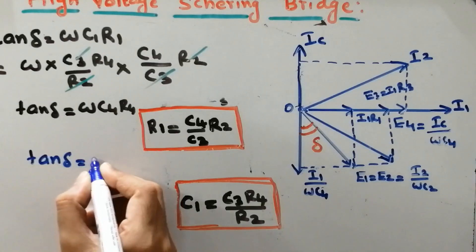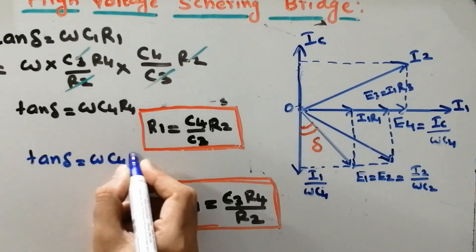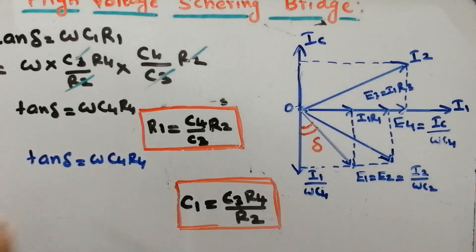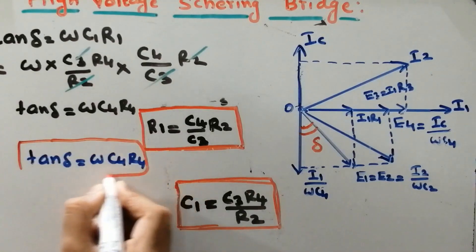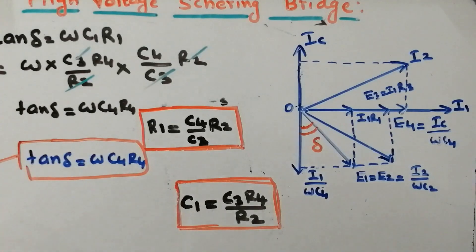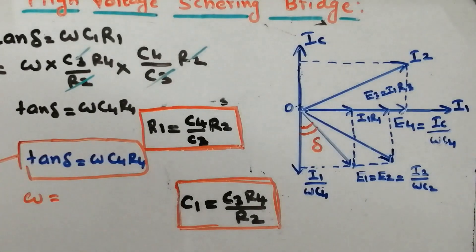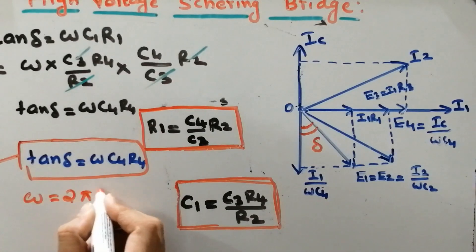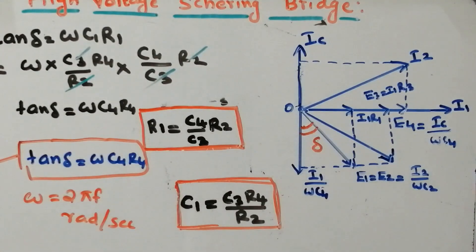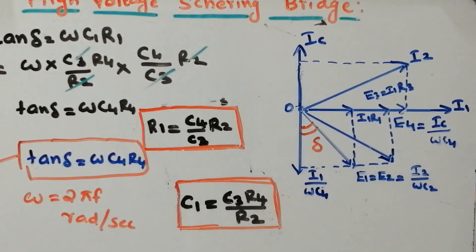Tan delta equals ω times C4 times R4. You can keep this equation in a separate block, as it will be helpful for solving numerical examples. Here omega is the angular frequency — if you know the supply frequency, you can easily calculate angular frequency as 2πf, normally expressed in radians per second. This is the way to calculate dielectric loss: tan delta equals ω times C4 times R4.